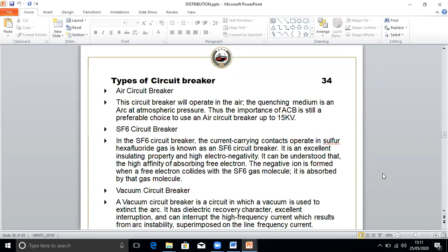Now the difference between both: vacuum circuit breakers are a little inferior to the SF6 breaker if you see voltage-wise. SF6 breakers are actually used for connecting the generator onto the switchboard. Whenever you want to connect the generator to the switchboard, we use an SF6 breaker, and the vacuum circuit breakers are used for interconnecting switchboards, like low voltage switchboards, starboard and port. For that interconnection we use a vacuum circuit breaker. It is of a little lower rated voltage.